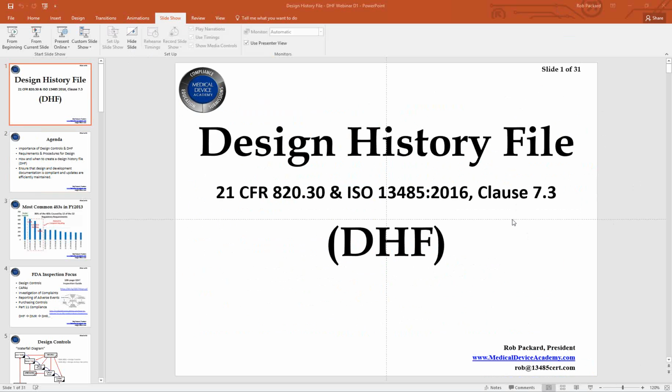Absolutely. You can certainly have documents in multiple places at multiple companies. They actually made it mandatory now in ISO 13485:2016 that when you outsource processes, you have to have a supplier quality agreement in place defining roles and responsibilities, and that would include the maintenance of records. So the DMR is a record of the most current version of the design and manufacturing process, and the DHF is the record of the design that was performed according to the design plan.